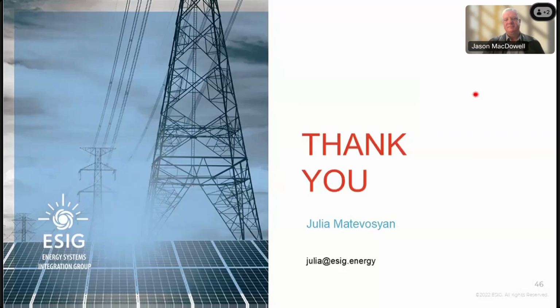So the only one, and I might have missed some because my focus primarily was on transmission level specifications, that talks about distribution level is ENTSO-E RfG 2.0, because it's requirements for all generators, so it includes very small generator sizes and down to distribution voltage levels. In that, they have a requirement for even those resources to be grid forming, but it's left to the national level to decide if it's going to be a requirement or not. So basically, they specify what grid forming means on that level, but as far as I understand, as of the current draft, the intention is that it's not enforced at the European level, and at the national level, it will be decided as needed. Okay, great. Yeah, thanks.